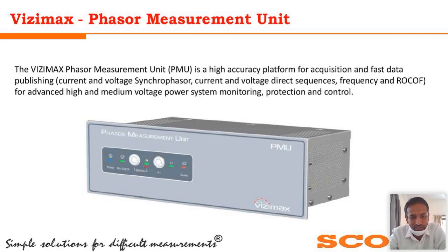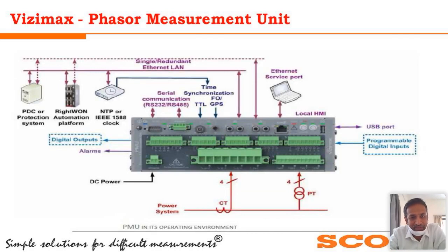I already explained what exactly a PMU is, so I'm skipping that here. You can see the backside of the PMU, with different ports. You have a time synchronization port, which will support the GPS signal and TTL signal. It will also support serial communication of RS-232 or 485, if you want to have some data on Modbus or on 104 connected to other things. We also have a C37.118 port as well as serial or RS-485 ports.